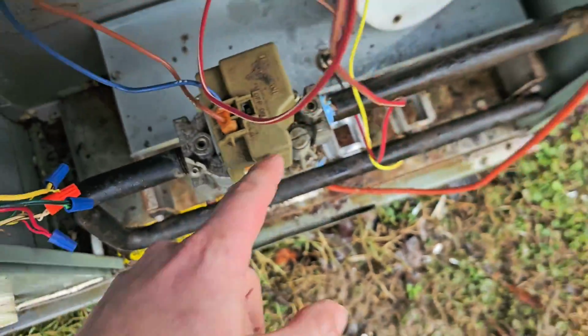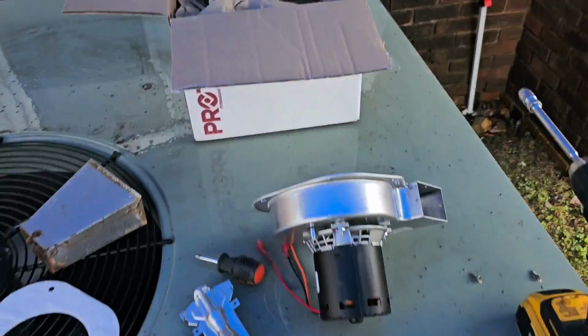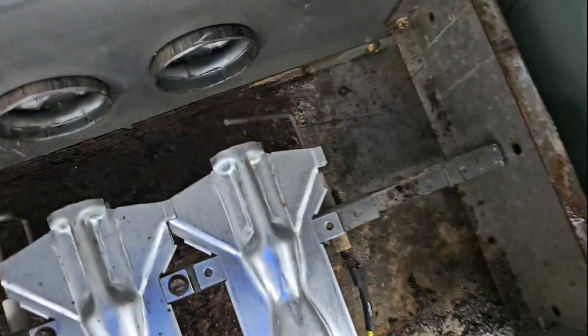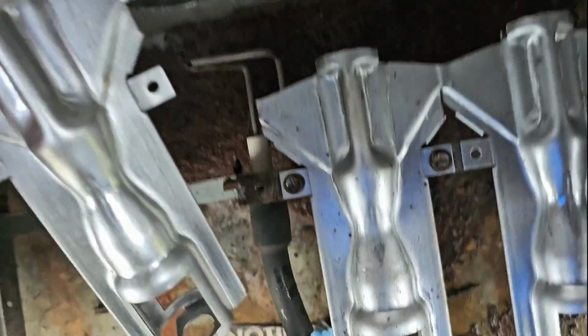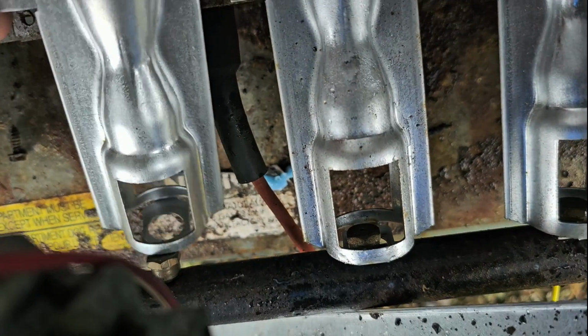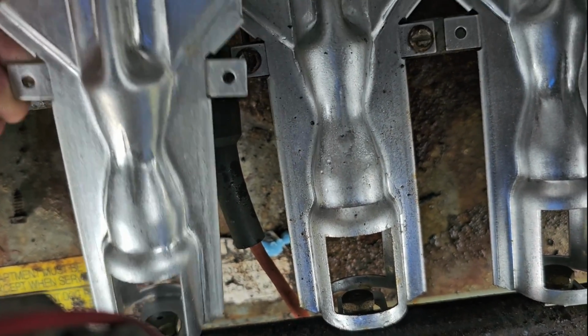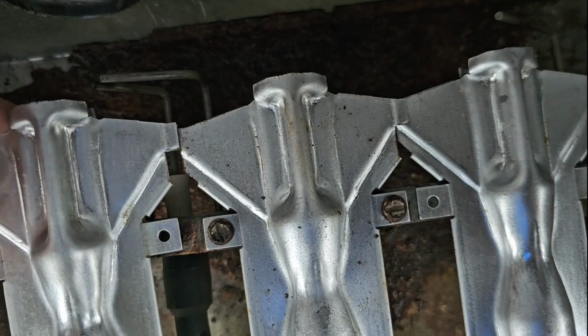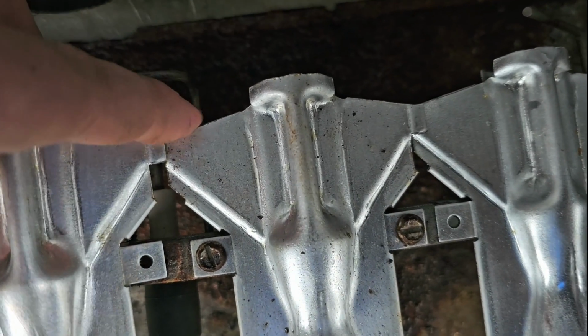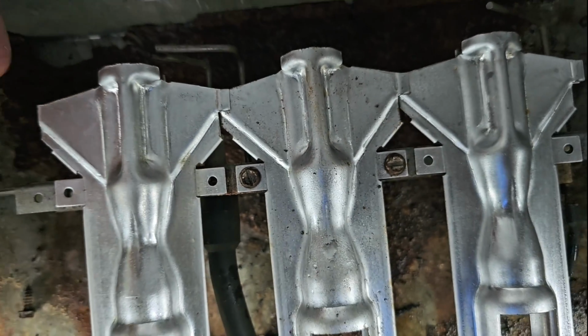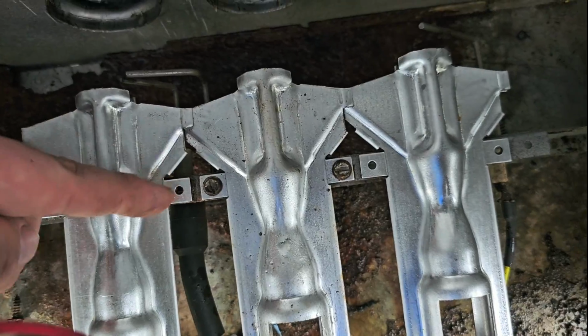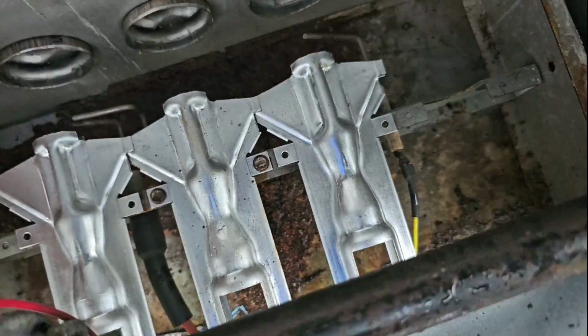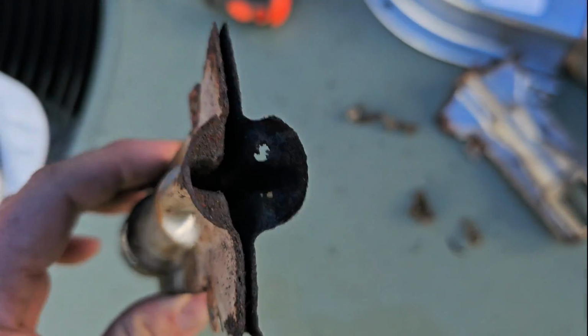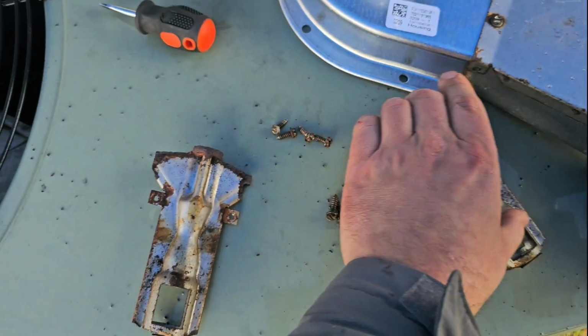So I'm going to go ahead and install the inducer motor, take this plate back off to get to the burners. Took that plate off so I can get to the burners, unscrewed the old burners, and you can see it's very easy to put on the new burner. You see it just slides right over that one, and then you've got two screws to hold that burner in place. There's the three new burners. There's the two old burners. Look at that. Definitely time to replace these.